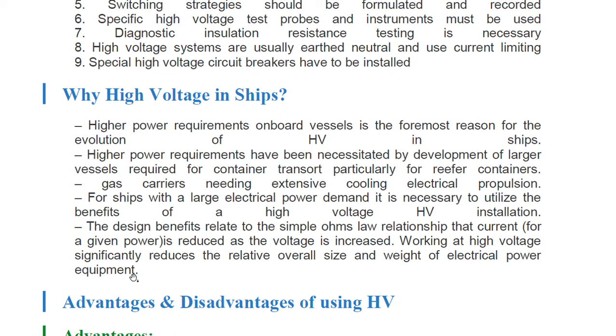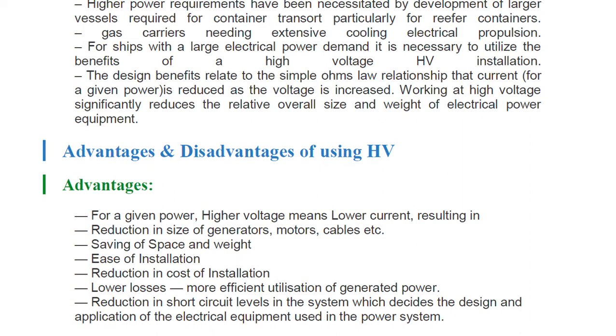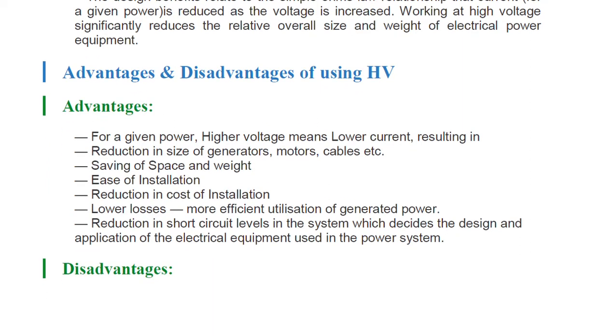The design benefits relate to simple Ohm's law: current for a given power is reduced as voltage is increased. Working at high voltage significantly reduces the overall size and weight of electrical power equipment. Advantages include: for a given power, higher voltage means lower current, resulting in reduction in size of generators, motors, cables, saving of space and weight, ease of installation, reduction in cost of installation, lower losses, more efficient utilization of generated power, and reduction in short circuit levels in the system.